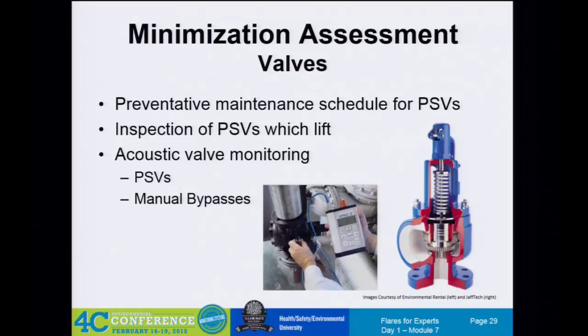One of the things you can do, especially if you're looking for high H2S leakers, is an acoustic technique. There's the picture of the VPAC 2. It uses not ultrasonics, but sonic detection to basically hear the turbulent flow of gas sneaking by the PSV. So you can find your leakers with that device. One thing we've heard from people is don't just do it on the PSV. Look at the bypass valve too, because a lot of times you'll change out that PSV every couple of years, nobody ever touches that bypass valve, and suddenly that's the one that's leaking. So it's good to check those as well.